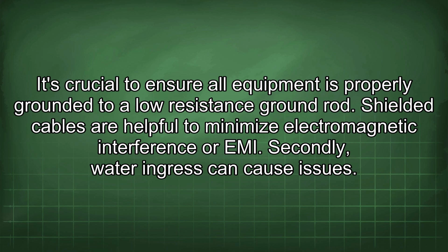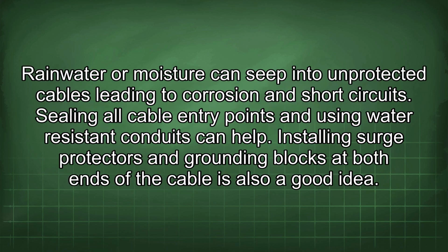Secondly, water ingress can cause issues. Rainwater or moisture can seep into unprotected cables, leading to corrosion and short circuits. Sealing all cable entry points and using water-resistant conduits can help. Installing surge protectors and grounding blocks at both ends of the cable is also a good idea.